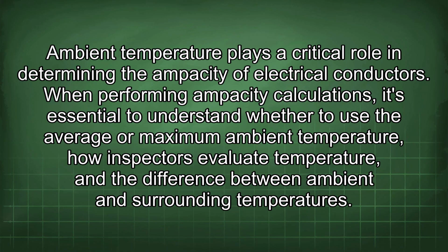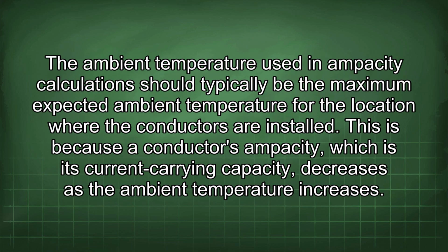Ambient temperature plays a critical role in determining the ampacity of electrical conductors. When performing ampacity calculations, it's essential to understand whether to use the average or maximum ambient temperature, how inspectors evaluate temperature, and the difference between ambient and surrounding temperatures.